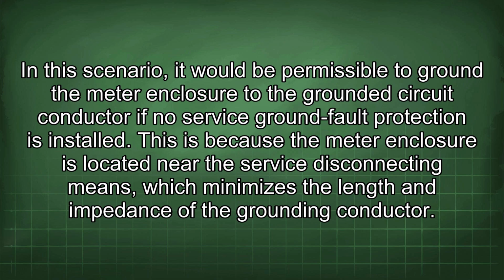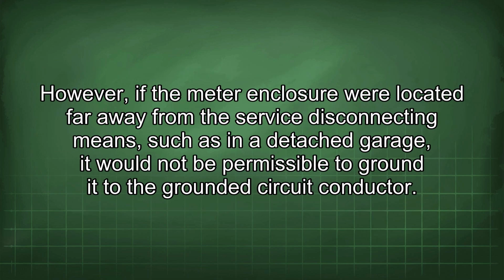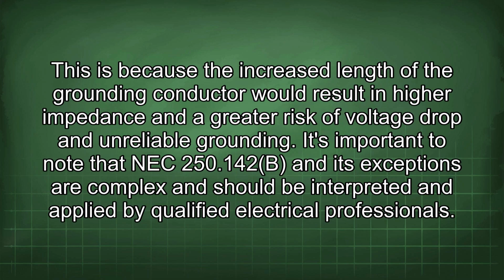This is because the meter enclosure is located near the service disconnecting means, which minimizes the length and impedance of the grounding conductor. However, if the meter enclosure were located far away from the service disconnecting means, such as in a detached garage, it would not be permissible to ground it to the grounded circuit conductor. This is because the increased length of the grounding conductor would result in higher impedance and a greater risk of voltage drop and unreliable grounding.